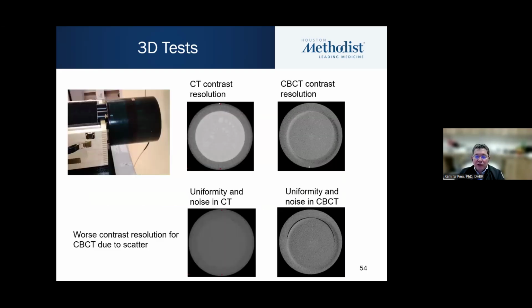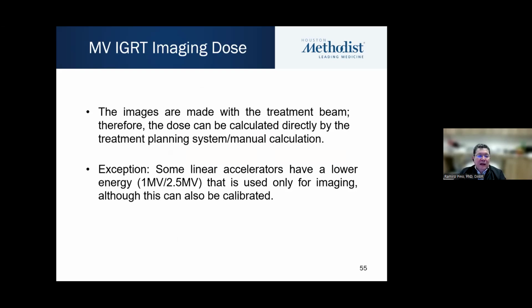As I mentioned, contrast resolution looks different in a CT than it looks in a CBCT. Typical CBCT has more scatter and more distortions. And as I mentioned, there have been significant improvements in the last year or so. MV IGRT imaging dose: most of the time we use the treatment beam for doing that imaging. So if we have a calibrated beam, which we're supposed to have, then it's straightforward to calculate dose based on the treatment planning system or manual calculations. The exception is that some linear accelerators will come with a lower energy beam that could be calibrated as well, but it's dedicated only for imaging, not for treatment.